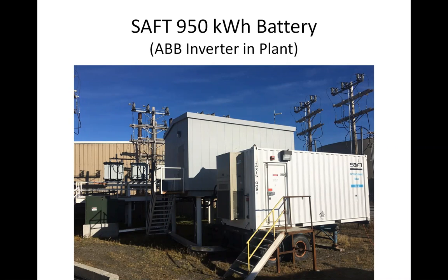So to heat it in the winter, we use jacket water heat. Out of this container, the lithium-ion batteries put out essentially 800 to 900 volts DC, which goes through a duct of copper cables connecting directly to the inverter. The inverter is in the powerhouse because that's where a lot of the control work is done, not so much in the battery itself. We wanted access to the inverter in the powerhouse, and I think that's the next picture.